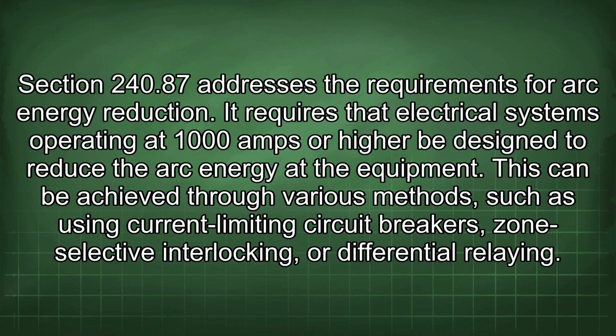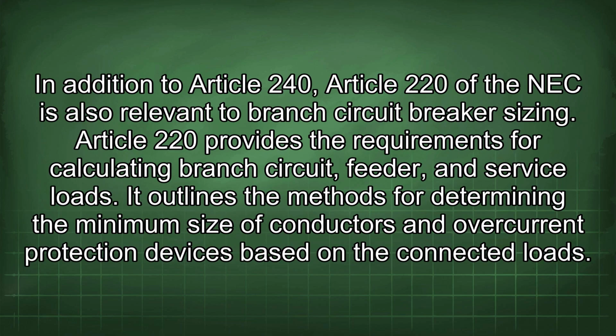It requires that electrical systems operating at 1000 amps or higher be designed to reduce the arc energy at the equipment. This can be achieved through various methods, such as using current-limiting circuit breakers, zone-selective interlocking, or differential relaying. In addition to Article 240, Article 220 of the NEC is also relevant to branch circuit breaker sizing. Article 220 provides the requirements for calculating branch circuit, feeder, and service loads.